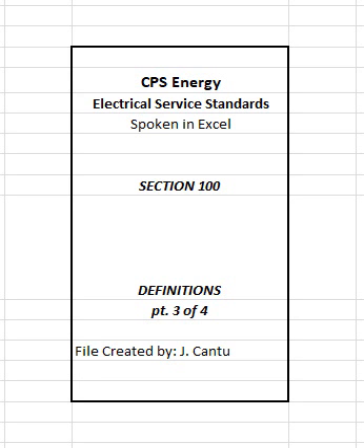D. Underground service from overhead distribution. Where an underground service is taken from a transformer or secondary on a CPS Energy pole in the overhead distribution area, the point of delivery will normally be at the meter equipment located outdoors on customer's building or structure. Where meters are grouped with wire gutters in accordance with Section 1800 and a bus gutter is used, the point of delivery will be in the bus gutter, or it will be in the main disconnect ahead of the gutter if one is required or installed. Refer to Section 600 for more detailed information.